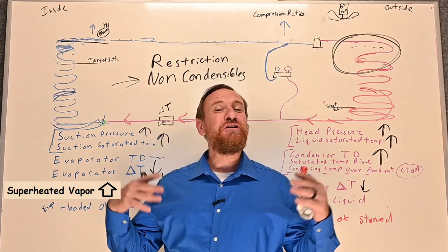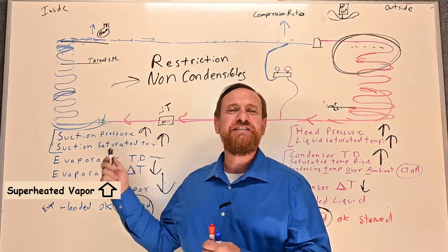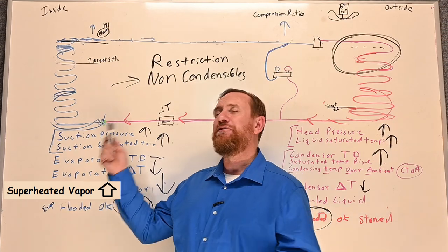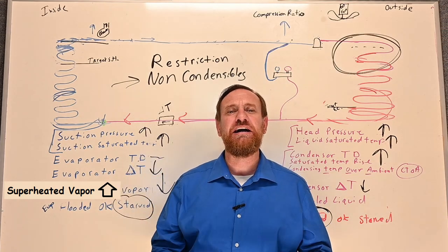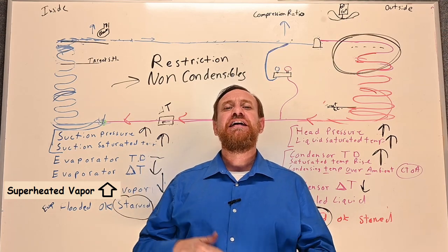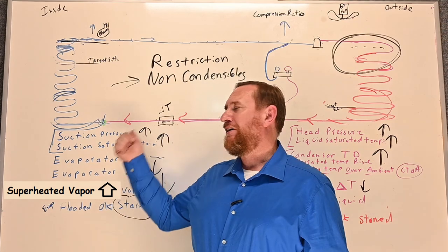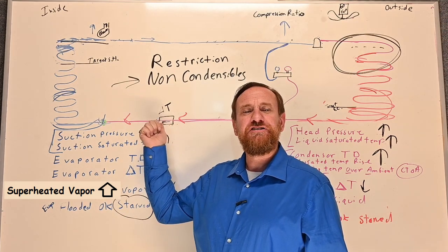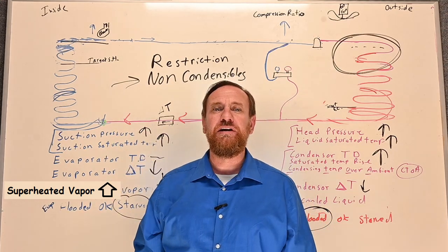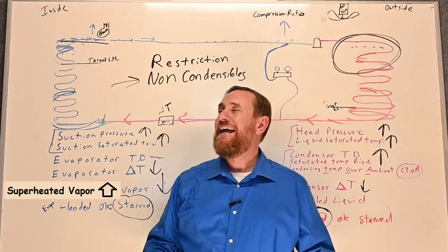One important note: when working with commercial systems dealing with hundreds of pounds of refrigerant, you would recover it, filter and dry it — which is called recycling — and recharge. That's because you're dealing with very expensive refrigerant in large quantities and refrigeration has a different level of rules. For residential systems with three to ten pounds of refrigerant, the cost of new refrigerant is nothing compared to the labor involved.